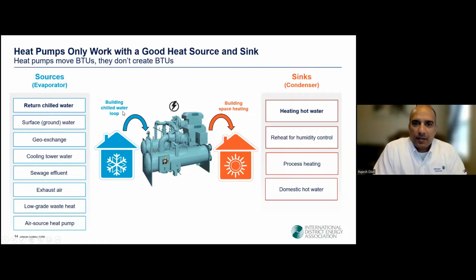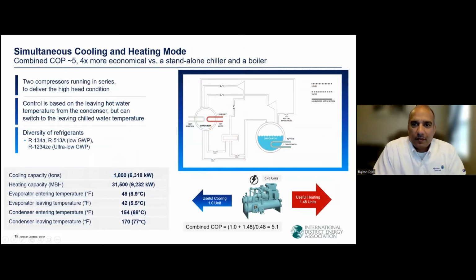So how does a water-to-water heat pump provide simultaneous chilled water and hot water, such as 42 Fahrenheit and 170 Fahrenheit, or 6 Celsius and 77 Celsius? As many of you know, typical air conditioning chillers are designed within the limits of the available compression ratio of the compressor.